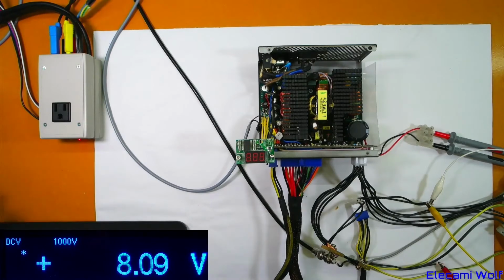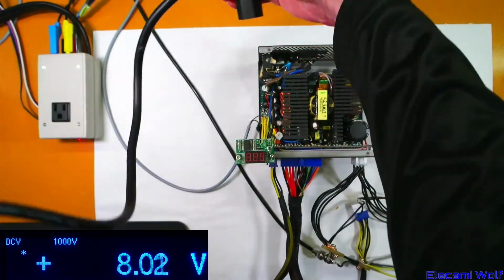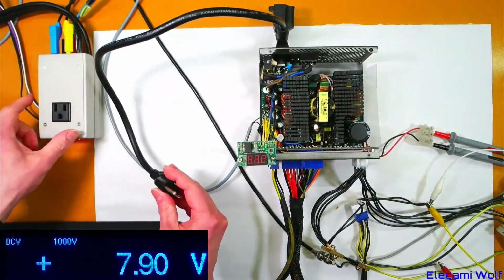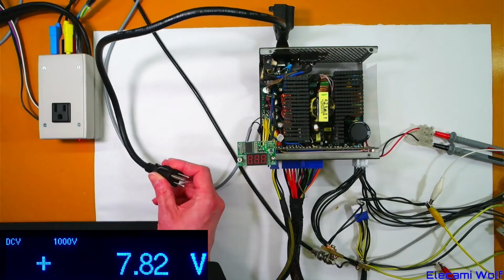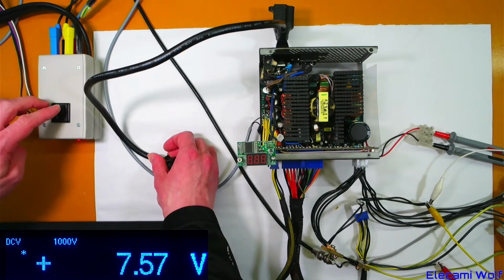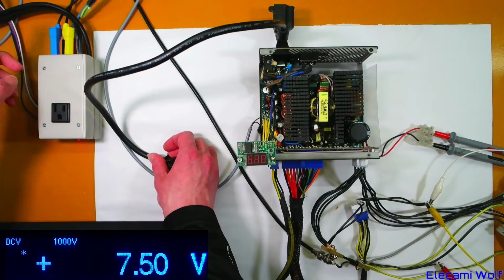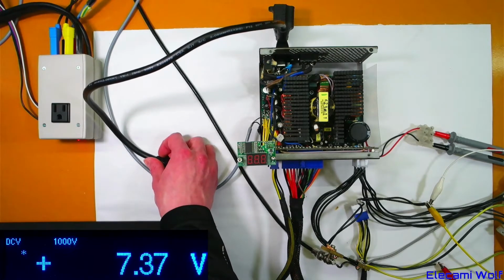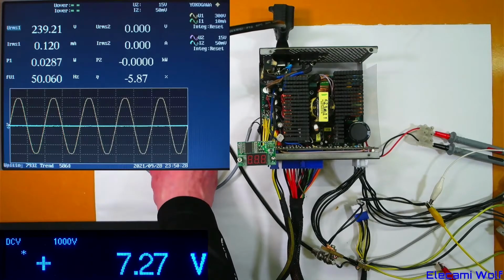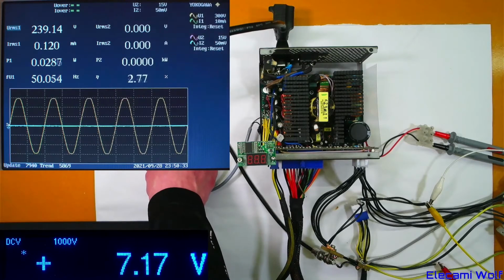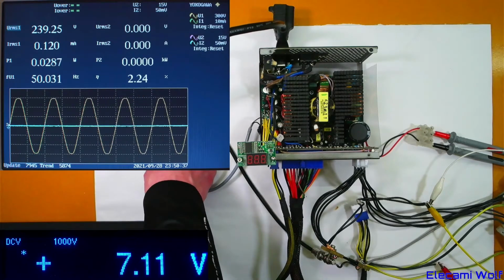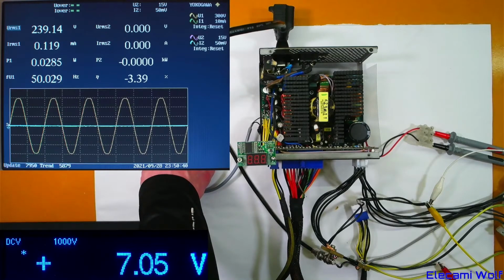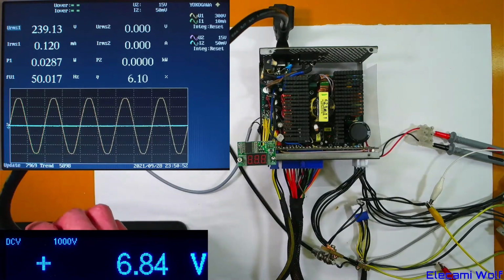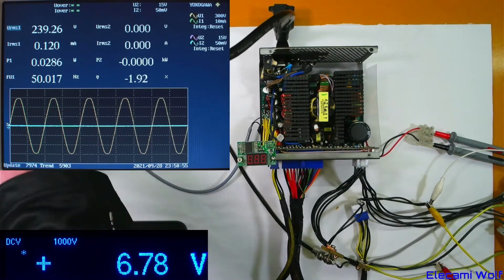For the AC input, I've got a fairly thick cable here, connected to this source, which is around 230 volts. It has a Kelvin connected voltage sense off the back of this socket, and also a link out to a current measurement. Those input and output voltage and current measurements go to a Yokogawa power meter here on screen. We can see down the left column the input voltage, current, power, frequency, and in the right hand column the output voltage, current, power, and a calculated efficiency. Below that we can see the waveforms, currently showing the input voltage waveform.